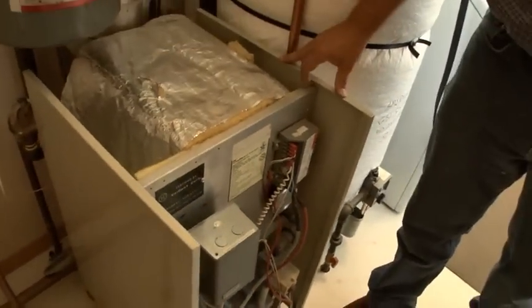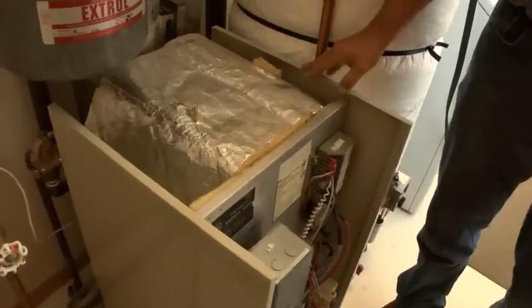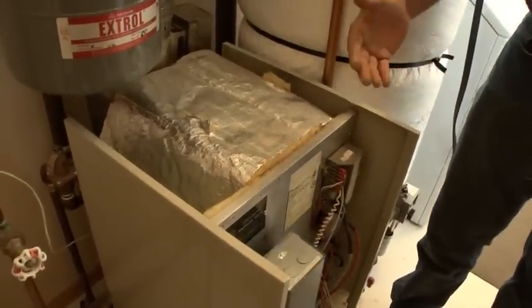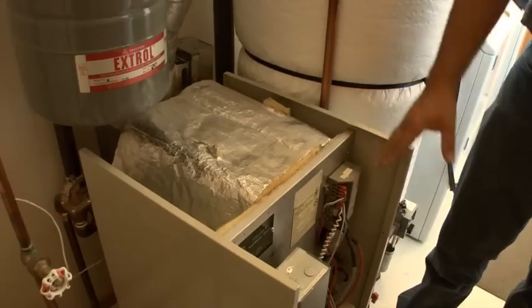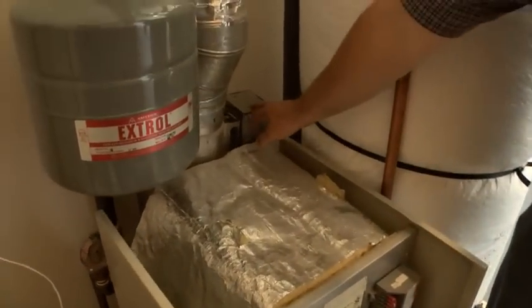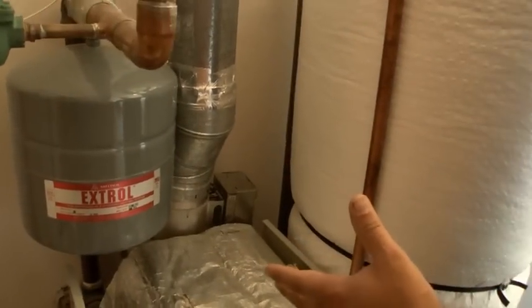And then also, to add a little bit of efficiency to this system during times when it's shut down and the pump's still running but the flames aren't running, is replacing this vent damper. There's some efficiency that can be gained. This thing's locked in the open position. You saw earlier how at 190 degrees the flame shut off, but the pump's still running. We still have a call for heat.